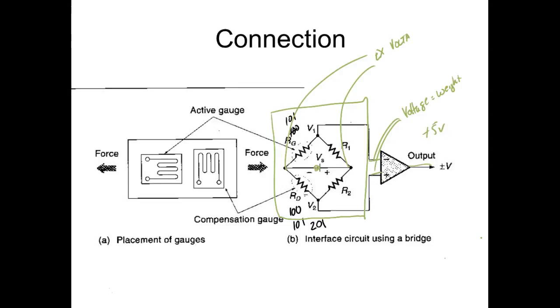And then we would put a certain amount of weight on there. Then we'd say that's the amount of weight. Then we'd reset zero. You have to do it about three times to set what we call the span of the scale. Once you got the span set, most scales have what they call an auto zero circuit on them. Because what happens with big truck scales? You get debris on the scales all the time. But there were motion sensors on there. If the scale started moving, it wasn't zero. If the scale wasn't moving, then every so often it would just zero to take out the debris.